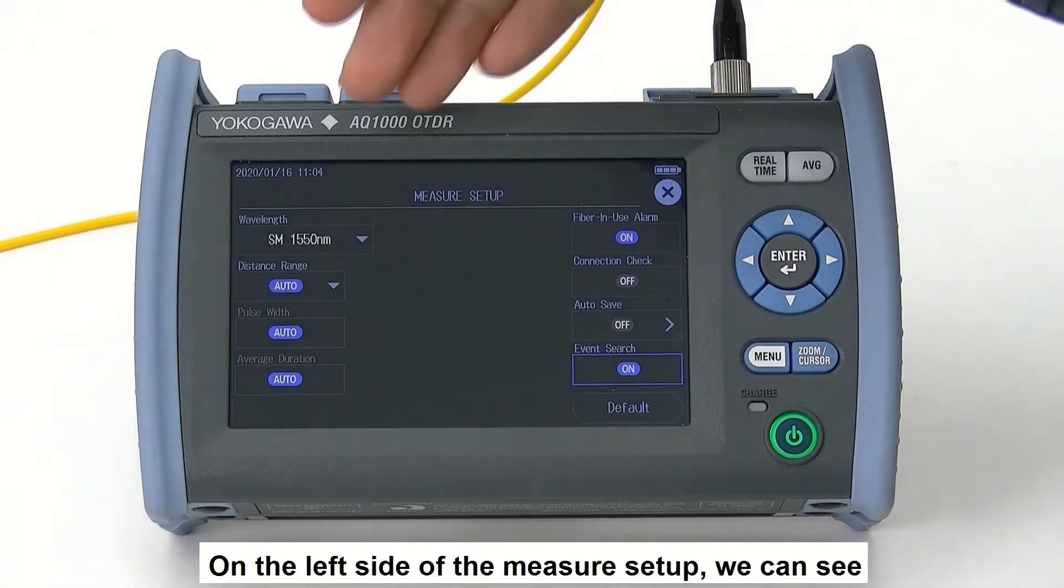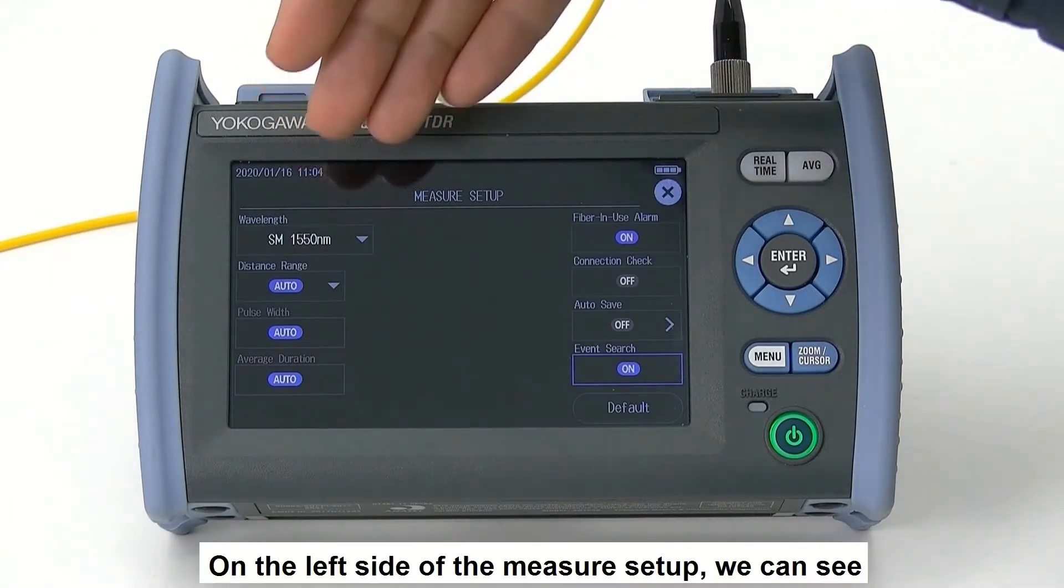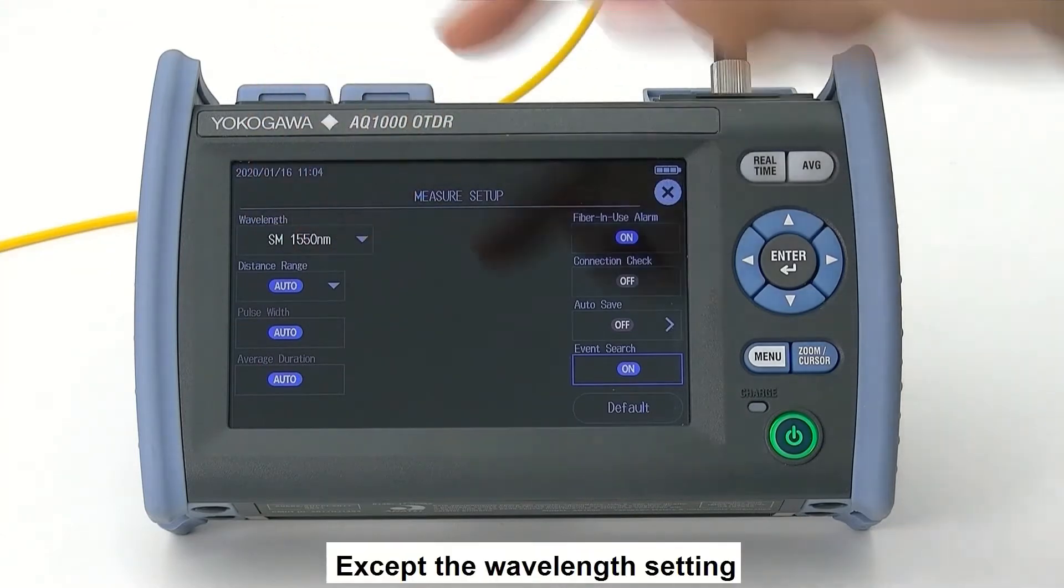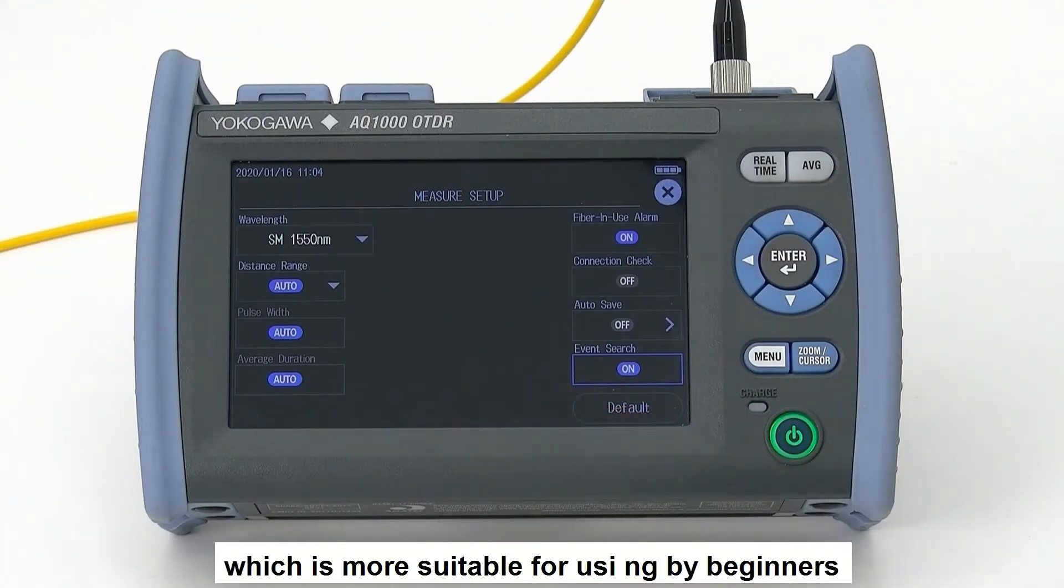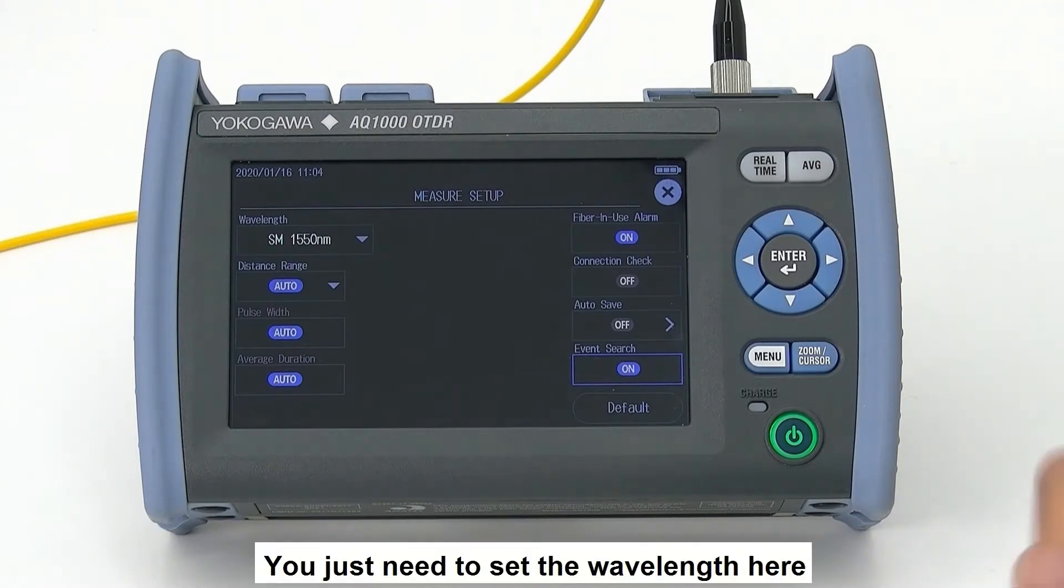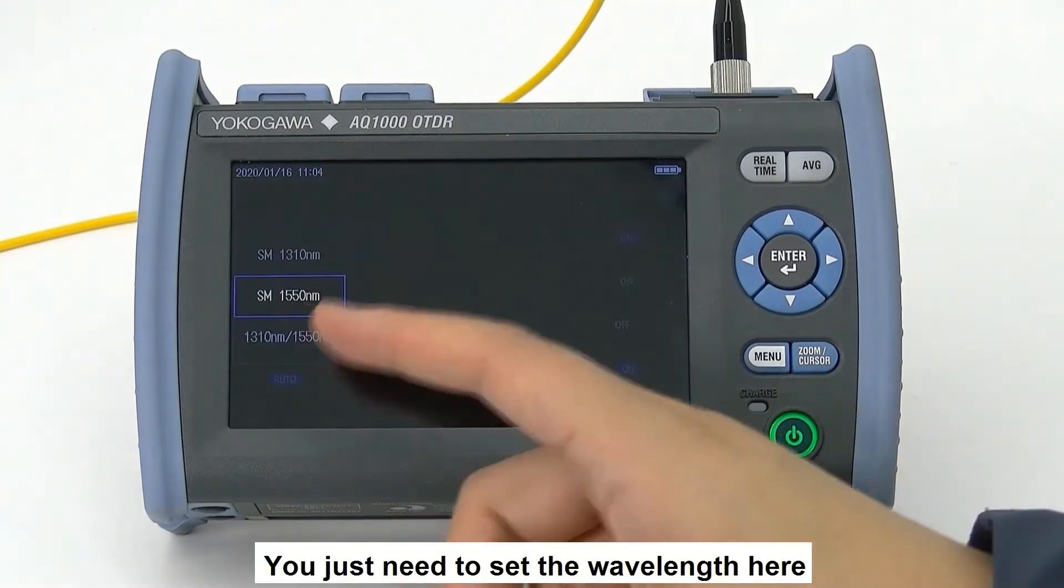On the left side of the measurement setup, we can see, except the wavelength setting, all other parameters can be set to auto, which is more suitable for beginners who are not familiar with the OTDR. You just need to set the wavelength.